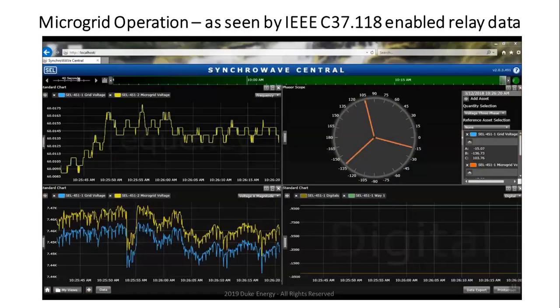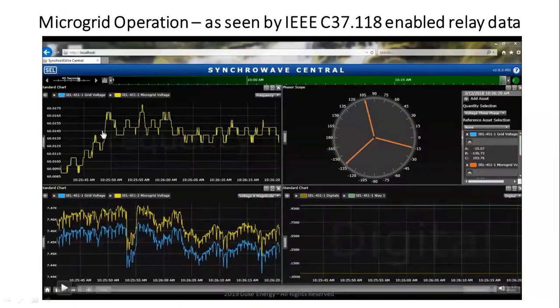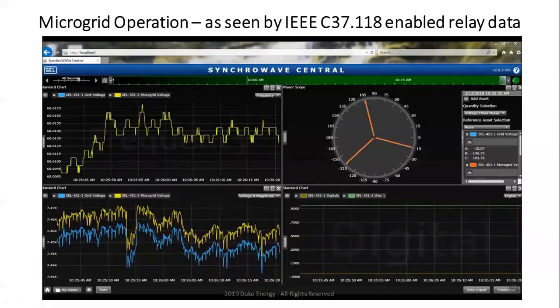And for those of you who have seen or who are familiar with IEEE C37.118, here is grid idling, seamless idling, and seamless grid resynchronization as seen by the synchrophasors, right? So just to show you what it is over here, on the top left side, you have frequency. Blue is grid, yellow is microgrid. They're on top of each other because PCC is closed, right? On the bottom left, you have voltages on both sides of the PCC. You can see that they're a little bit different, but right now the PCC is closed, so they should be on top of each other.